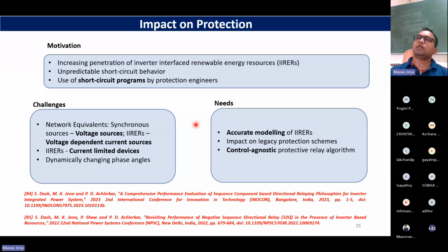Similarly, if there is any unbalanced fault happening in the system, we expect that along with the positive sequence quantities, there will be negative and zero sequence quantities. These are the default expectations. But is this correct for inverter-based resources? That is what we need to look into, retrospect and brainstorm.